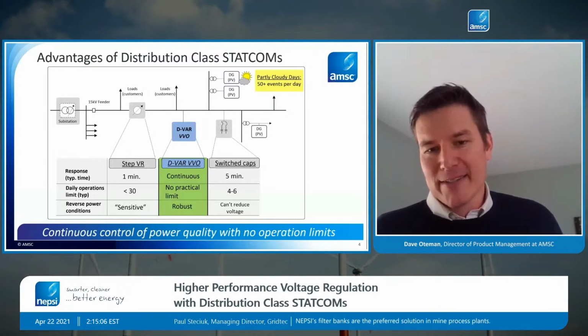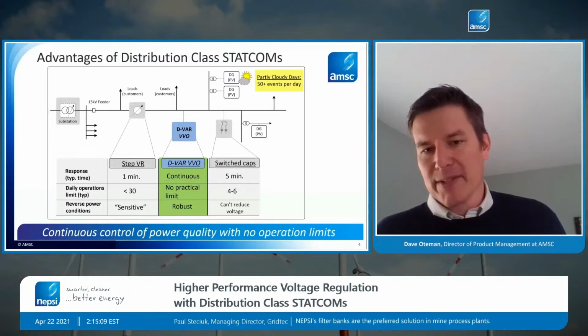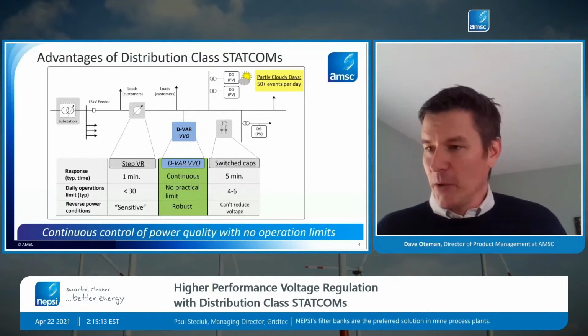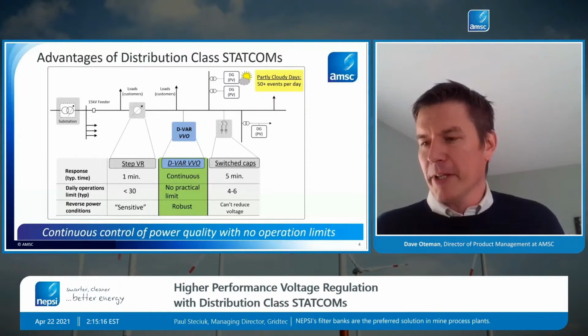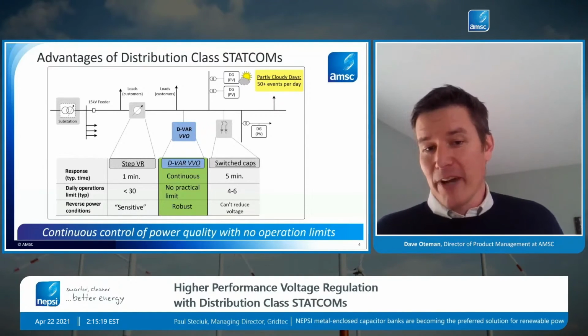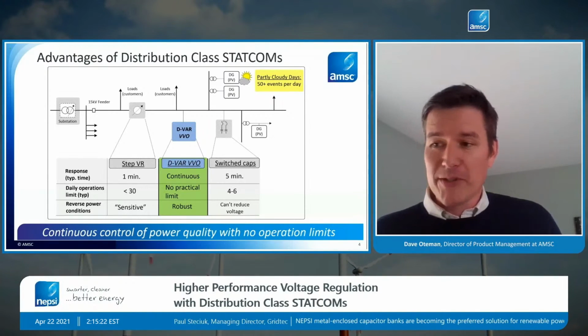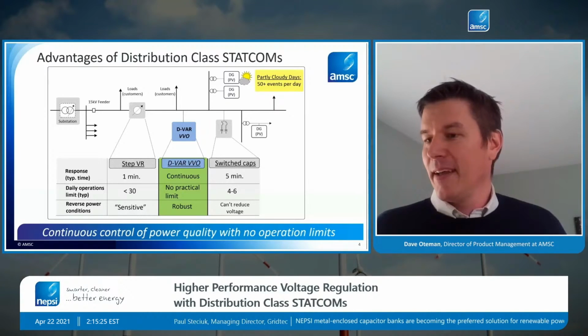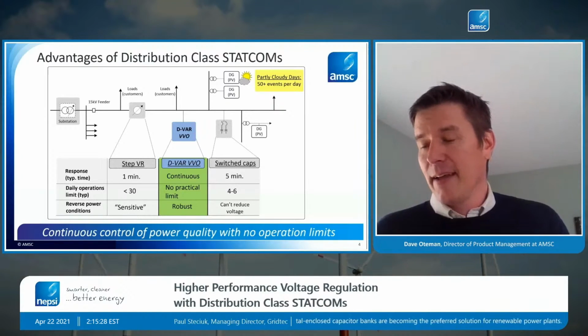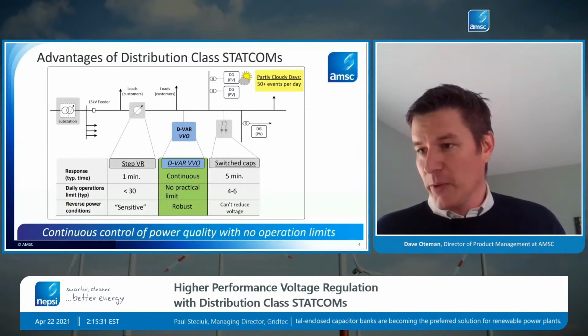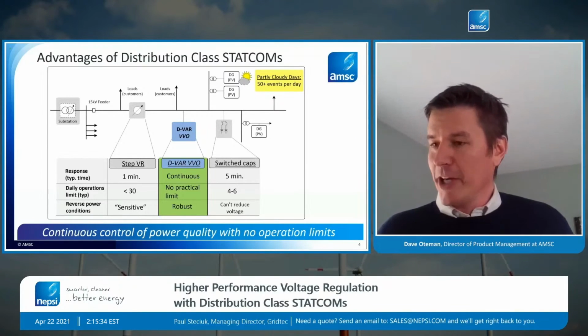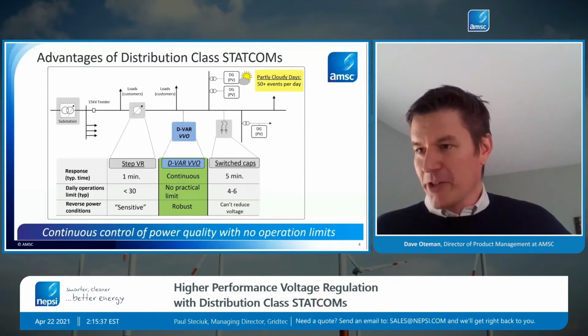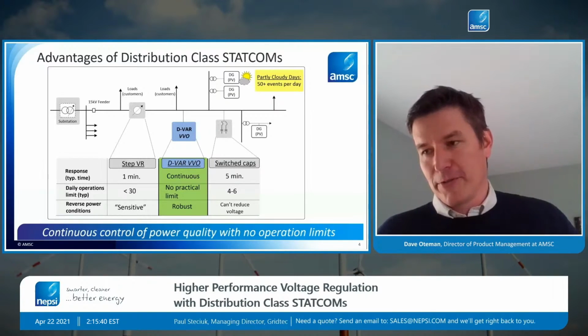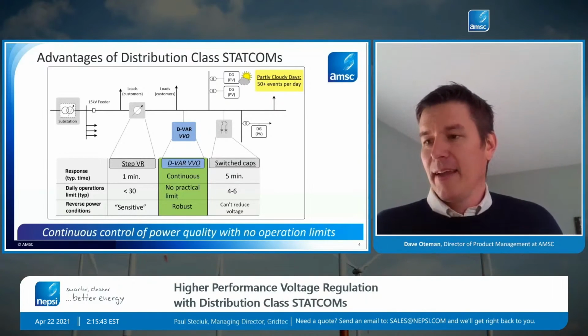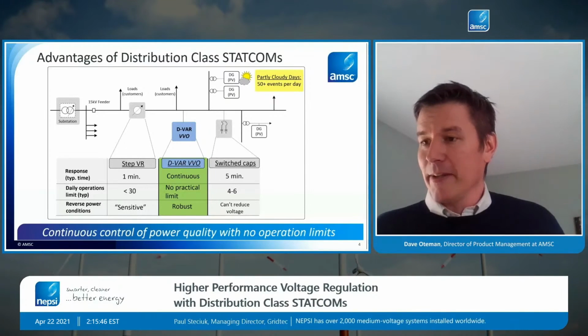So a power electronics device really addresses this gap that we see in the existing line regulation equipment that utilities use. And that's what's shown in the middle of this graph here. A power electronics device is able to continuously control. Thousands of times a second, these power electronics sense and react to the voltage changes or the VAR changes continuously. No practical limit on operations. So as we get these larger fluctuations, whether they're driven by solar or by high throughput industrials, power electronics is not sensitive to that. That's a big advantage, and why our customers like our solution.